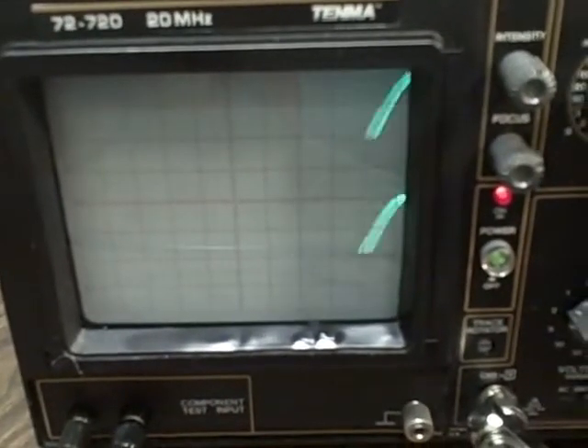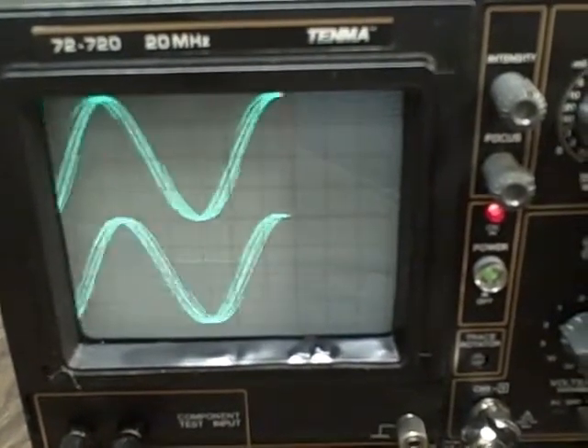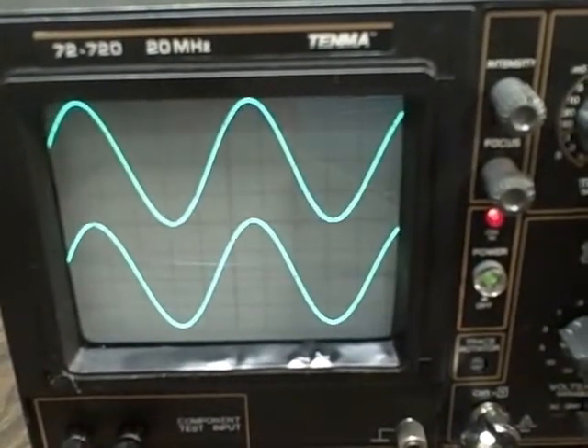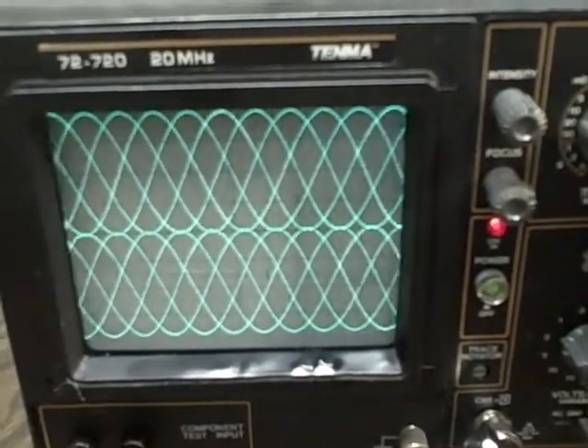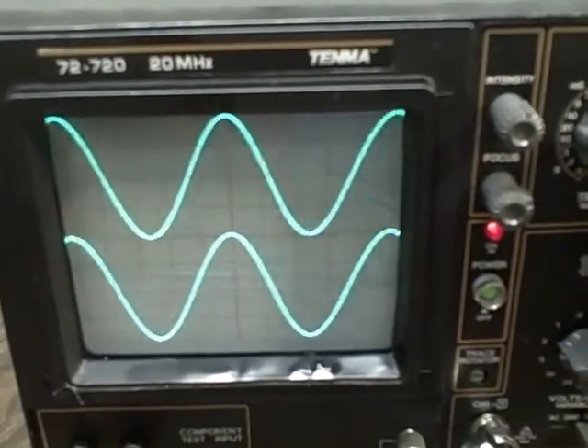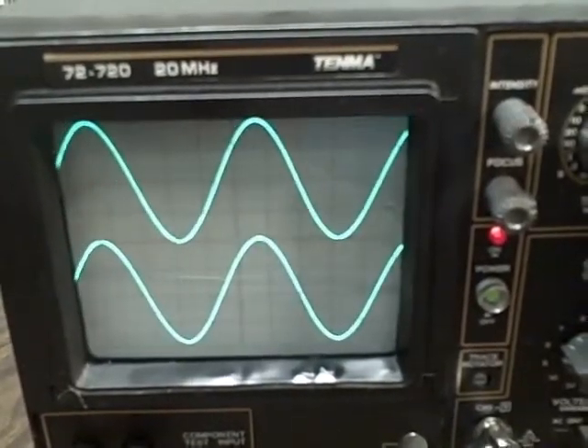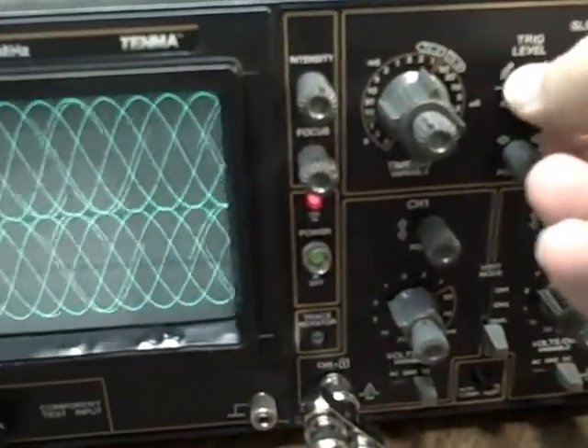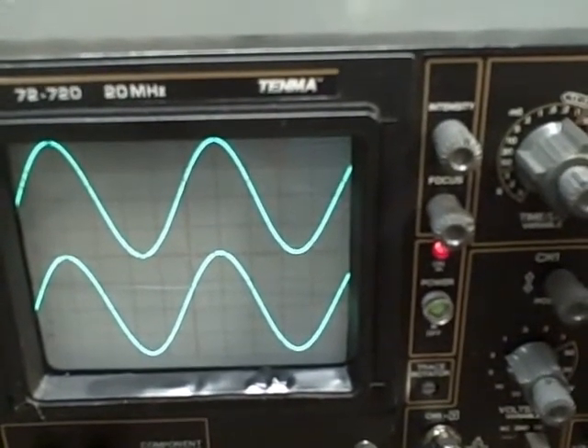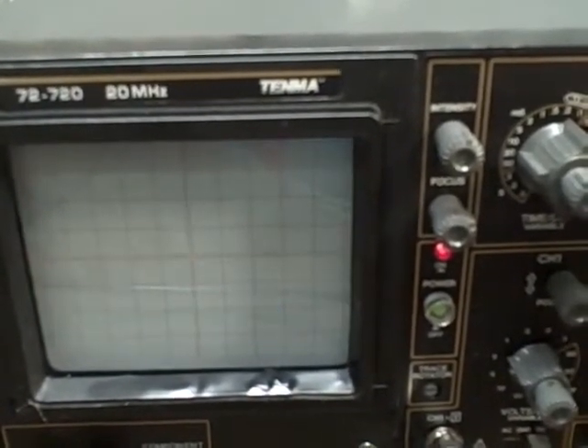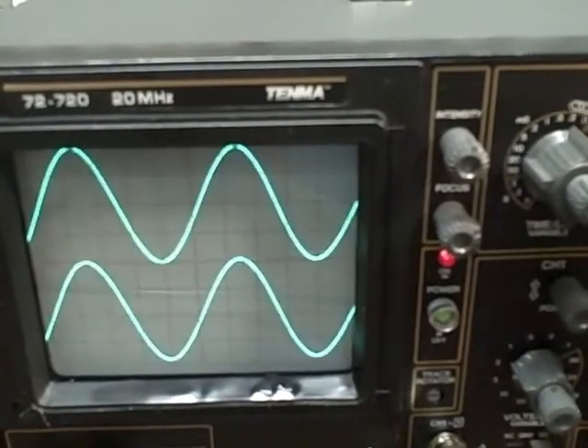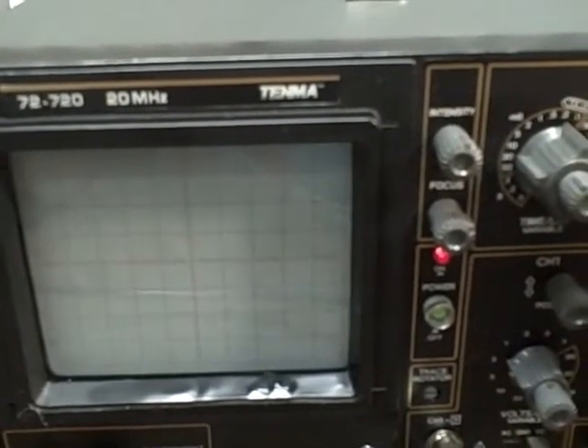We have a horizontal adjustment capability. We have trigger, this is in the automatic mode so you can see the trigger loose, or we can put it in normal mode where if you don't have a triggered trace you don't get a trace at all.